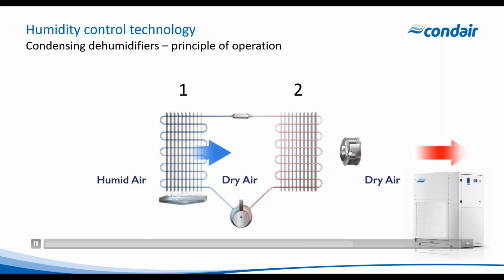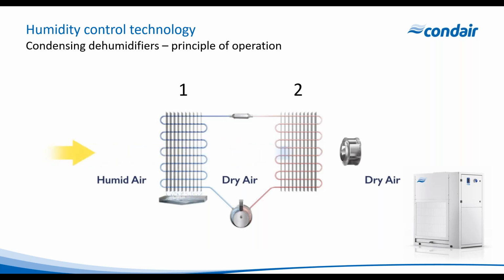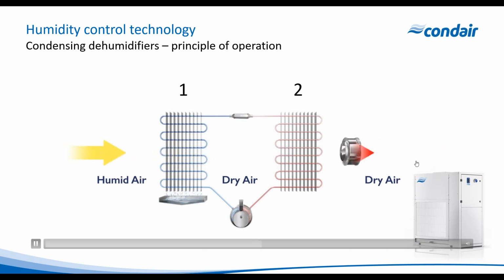Now, it's a really important consideration to understand that you will always get a heat gain, because as condensation forms on this evaporator coil, the latent heat of vaporization will be released into the air. So as water changes from its gaseous state to its liquid state and condenses on that coil, heat energy is released. So with every type of condensing dehumidifier, you will always get a heat gain. And this should be considered in the design of the unit and the space.